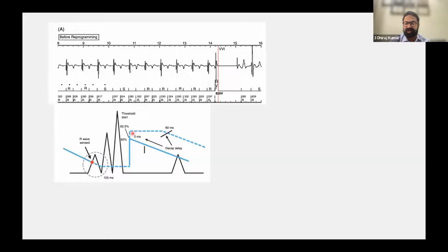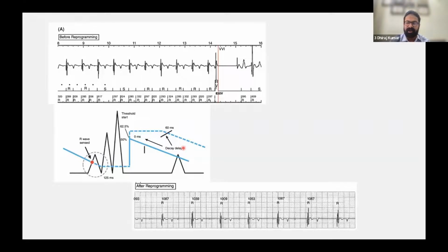So the programming change we made was, rather than 0 milliseconds at the start of the decay, you delay it by 60 milliseconds. That means the fence is over the height that the dog can jump, and therefore it misses the T wave and you do not detect the T wave. And bingo, voila, after you reprogram it, the T waves are not being detected by the device, and this is how one can abort a therapy.